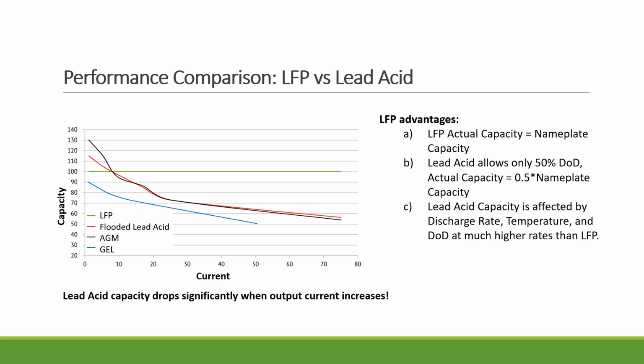Here's a graphic that shows how the capacity changes when you start to draw more power, or higher amperage, out of the battery. With lithium, as long as you stay within the BMS parameters, for example, a 200 amp hour battery, if you discharge at 100 amps, it will last for 2 hours. So you can expect 2 hours. With other types of lead acid batteries, the capacity will drop. So you might expect it to last 2 hours, and all of a sudden it may be only 30 minutes. That has a big impact if you are, for instance, down in the south in summer and want to turn on your air conditioning. That's really going to make the battery last much shorter than you would like.